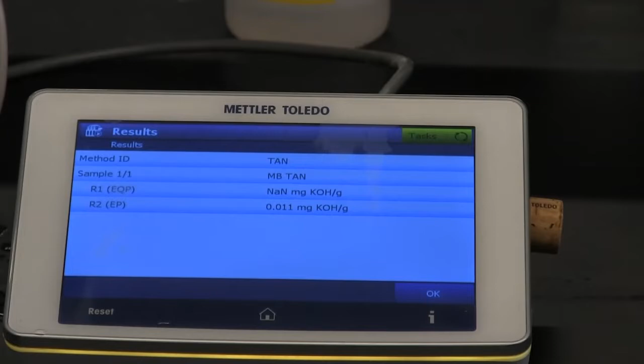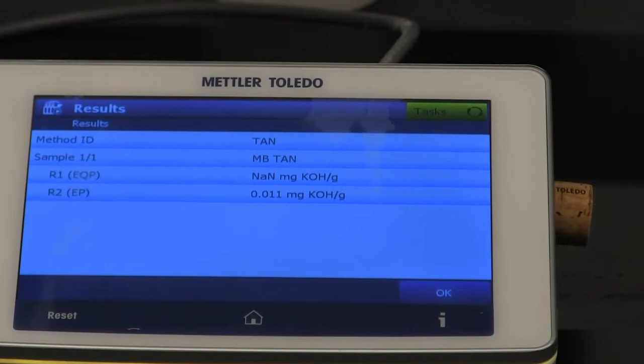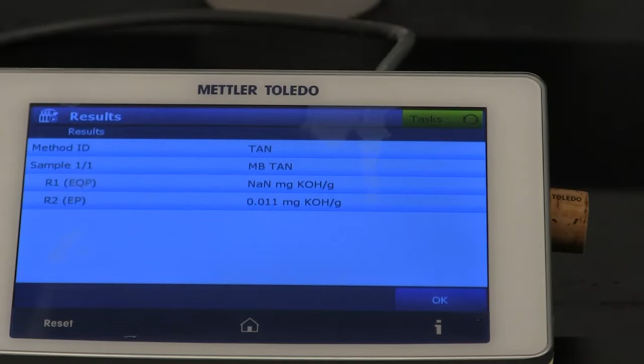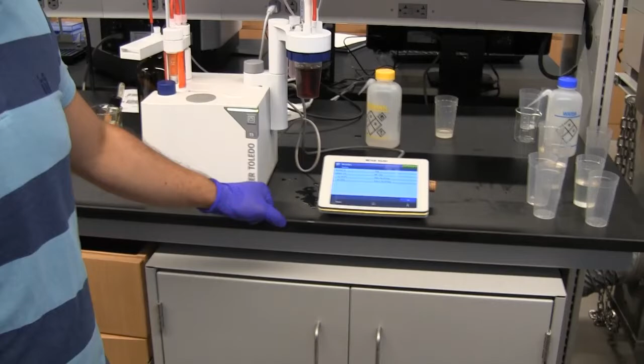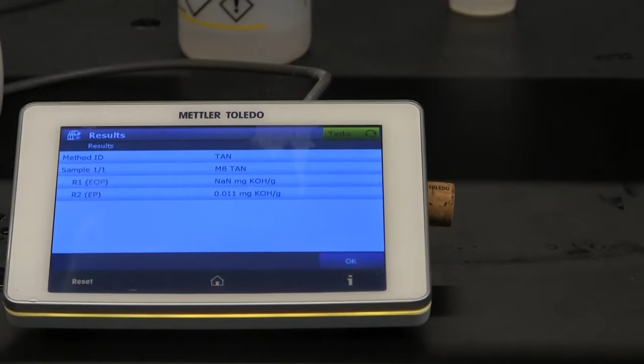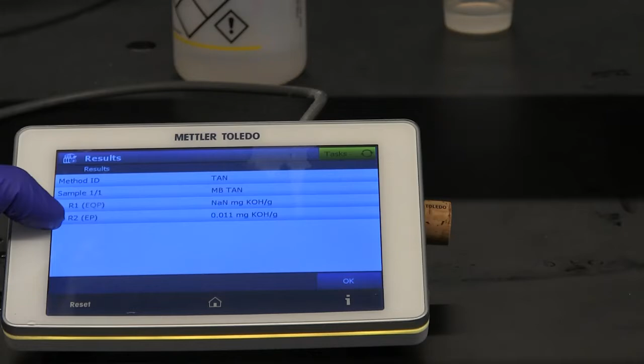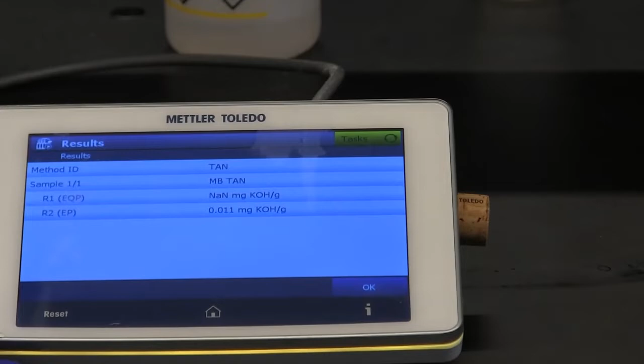So in our case, it didn't find an inflection point, which means once you get R1 is not a number and R2 is a very low number, that means your acid number is below this value and is probably below your detection limit. We actually added the maximum amount here in the table. We can still increase it, but I don't think we are going to reach anything else. The acid number is lower than 0.011. So your acid number should be the equivalence point, but since it's not detecting anything, we are going to report that it's just lower than 0.011. And that should be it for the measurement.